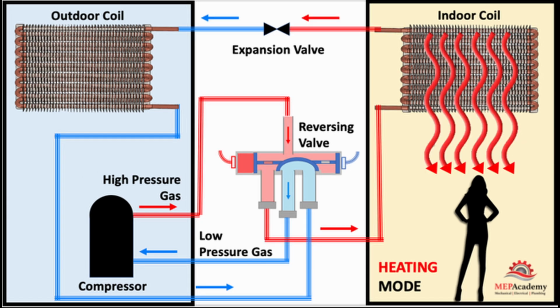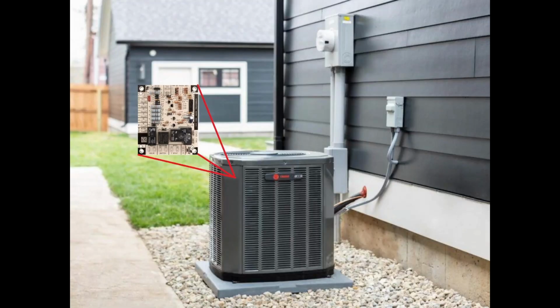But when the reversing valve is called into heat mode, the outdoor coil collects heat from the outdoor air and the indoor coil rejects heat into the space you are trying to warm. So your evaporator coil is actually outdoors when you are in heating mode. On an air-to-air heat pump, you must have a defrost board because ice will eventually form on the outdoor coil and will need to be melted periodically. A water source heat pump has no need for a defrost board. No ice will ever form around the coil when the unit is in heat mode. The temperature and flow of the water loop will prevent that.